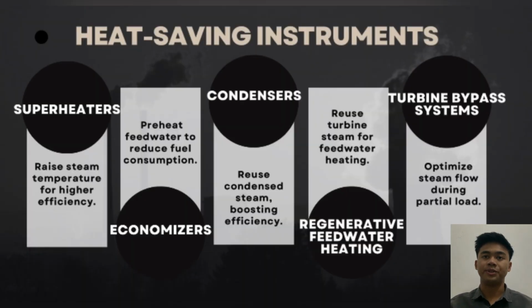Heat saving instruments. Superheater: superheaters raise the temperature of steam beyond its saturation point, increasing thermal efficiency by preventing moisture in the steam, reducing turbine erosion, and improving heat transfer in the boiler. Economizers recover heat from the flue gas leaving the boiler and use it to preheat the feed water before it enters the boiler. They reduce the amount of energy required to raise the water to the desired steam temperature, thus improving overall efficiency.